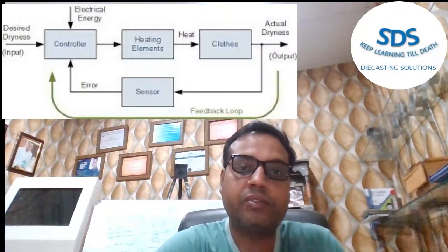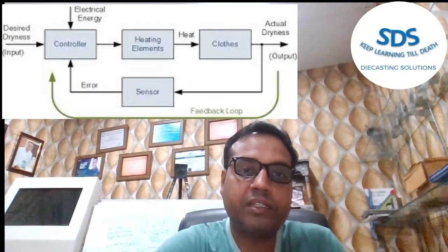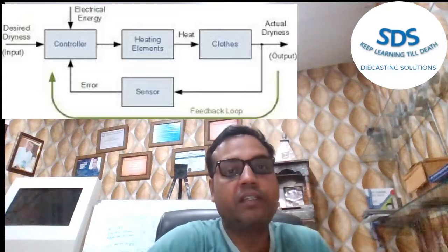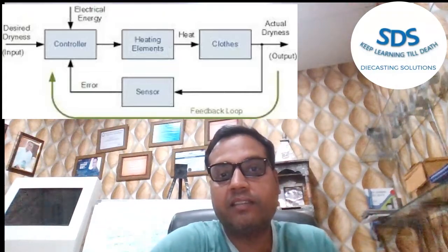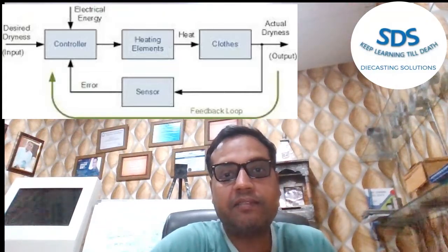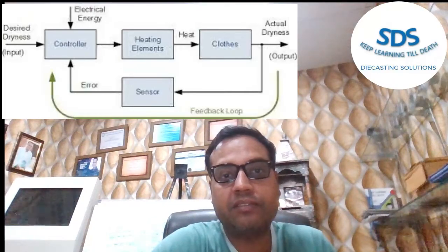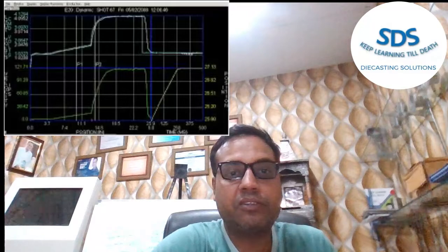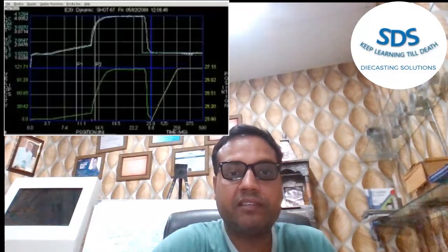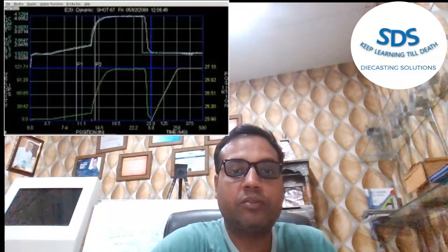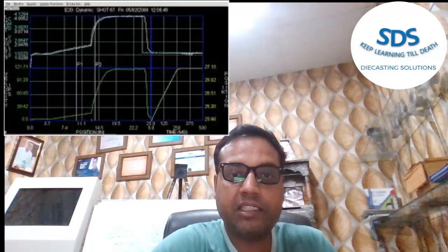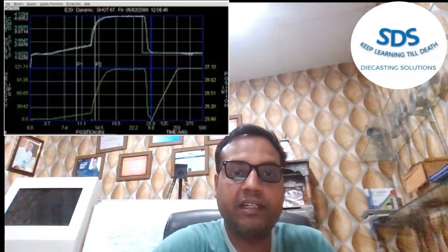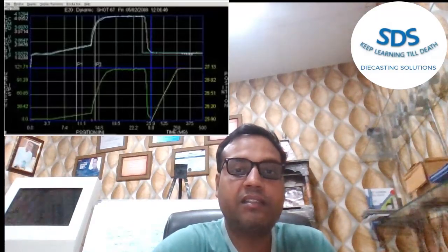If the closed loop control system does not have a reaction time — which includes the reaction of electronic and hydraulic components — that is at least four times less than the desired fill time, then closed loop control should not be used. This is because the closed loop system will not have a chance to make adjustments if the fill time is too fast relative to the reaction time.